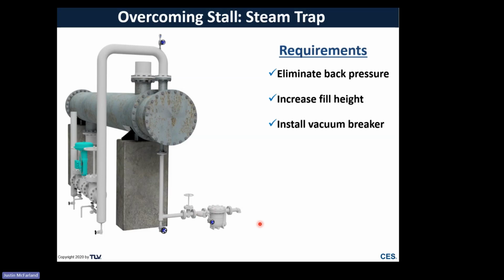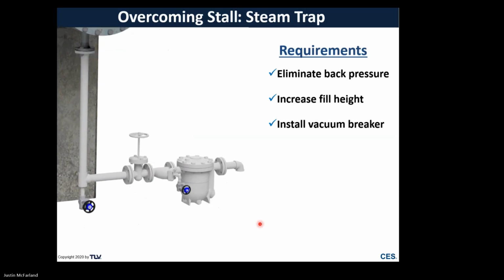So the caveat here is that for the trap that's selected, you absolutely need to make sure it's got an integral air vent, and it can operate under normal steam pressure conditions. What's probably going to happen is that the process control is going to see that air is in the system. The process temperature will slowly begin to cool down a little bit, and then the control valve will begin to open up a little bit and try to force that air out. If that air can't get out, well, then that effectively vapor locks the system, and now we've got air stuck here, all the while condensate is still being produced by the process heater, but now it's backing up again into the heat exchanger, and so that becomes problematic.